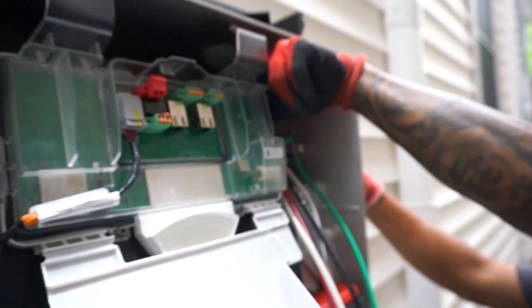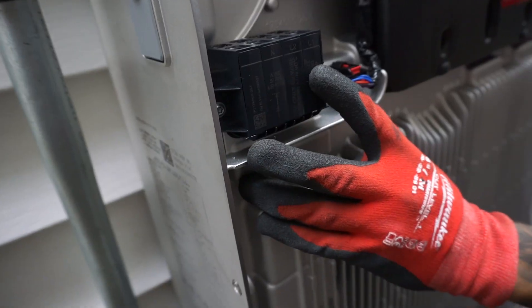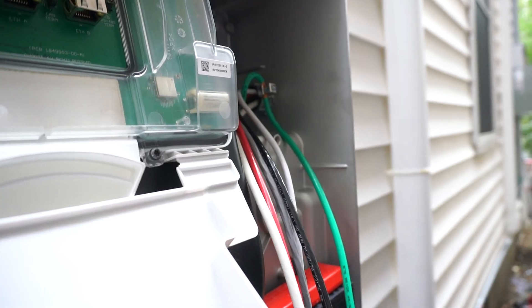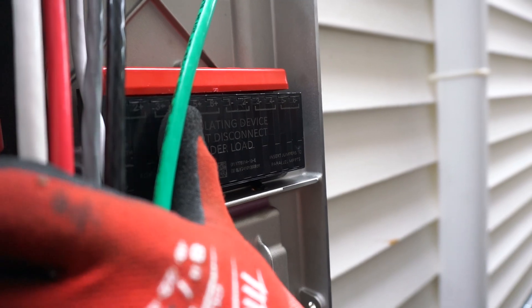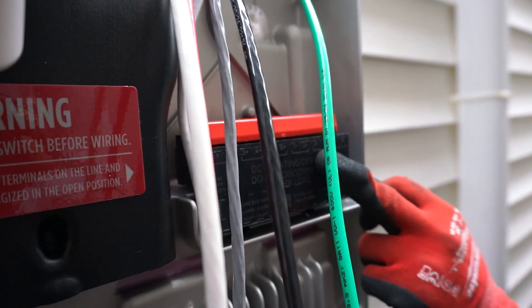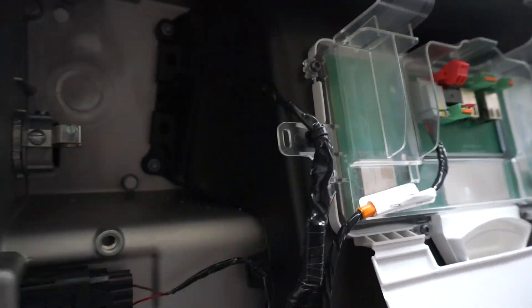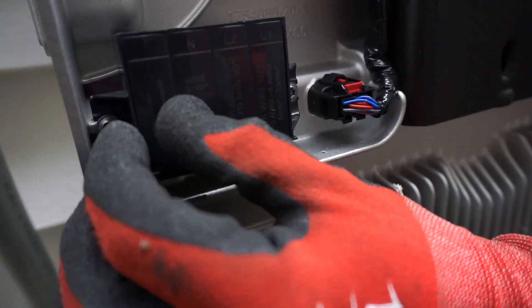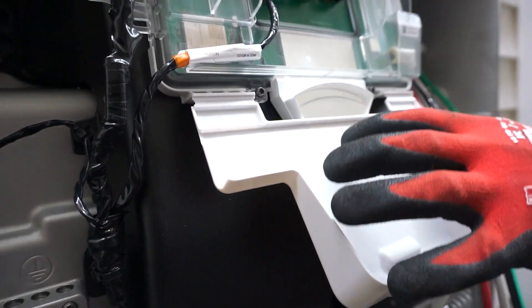Your actual feeds come back tucked here — neutral, line one, line two. Here are your DC terminals: line one, line two, three and four, with negatives on this side. These come right back behind the bus, and this will feed your lines — line one, two, neutral, and ground terminals. You'll have your ethernet port and comms kit here at the top.